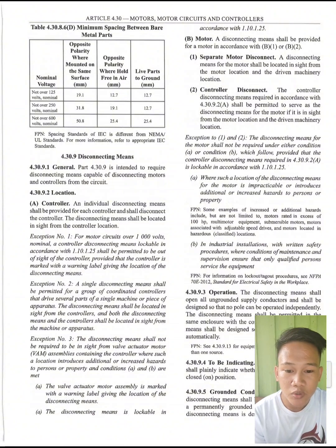So, exemption number 2. A single disconnecting means shall be permitted for a group of coordinated controllers that drive several parts of a single machine or piece of apparatus. The disconnecting means shall be located in sight from the controllers, and both the disconnecting means and the controller shall be located in sight from the machines or apparatus.